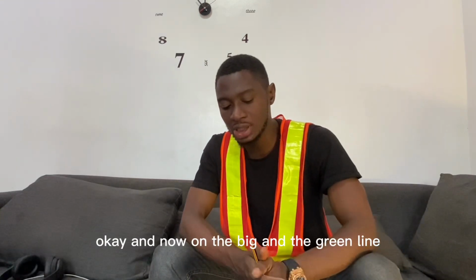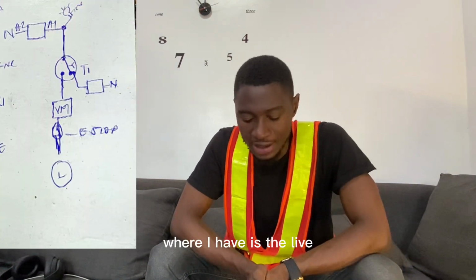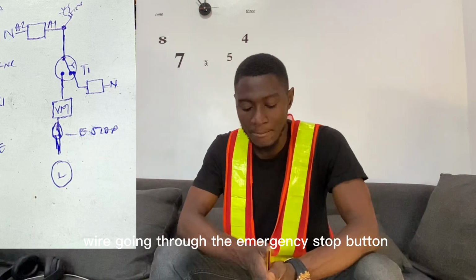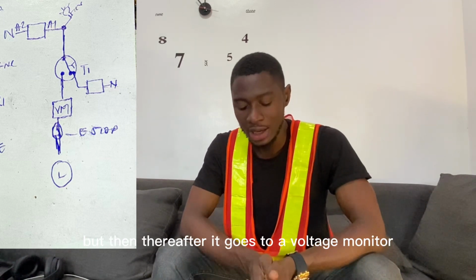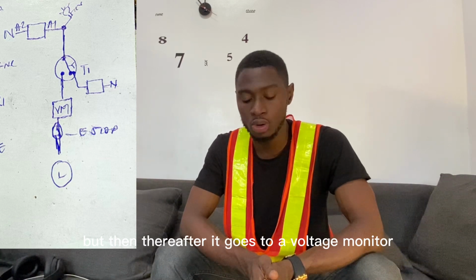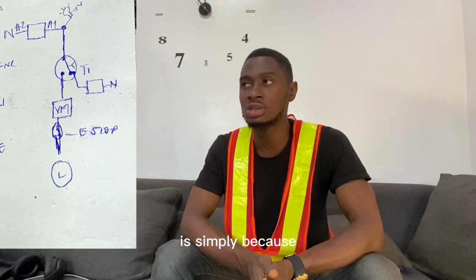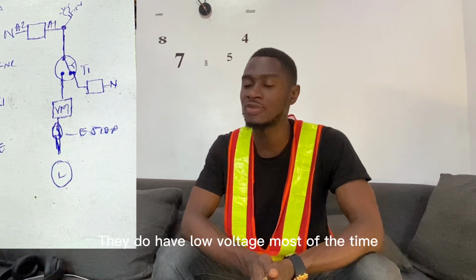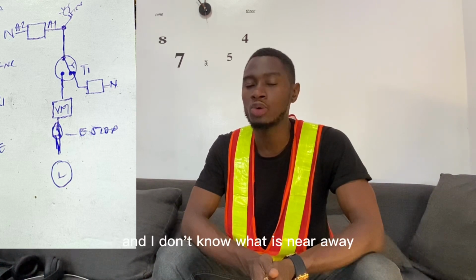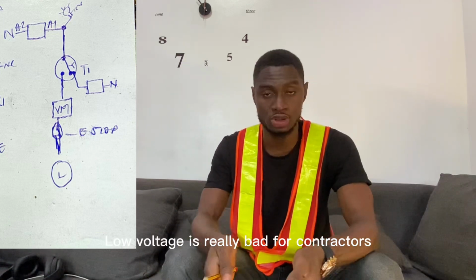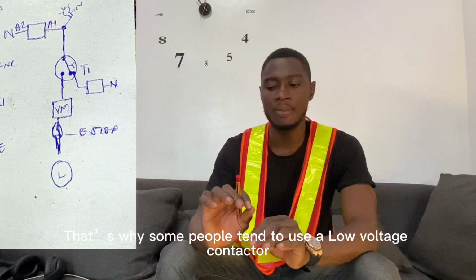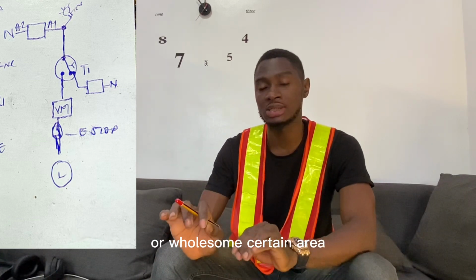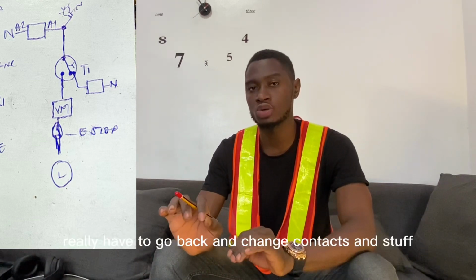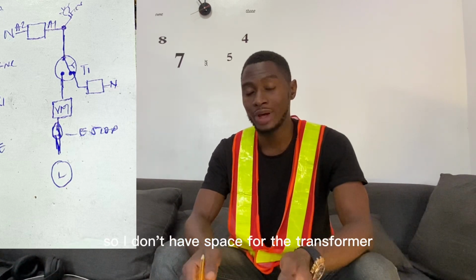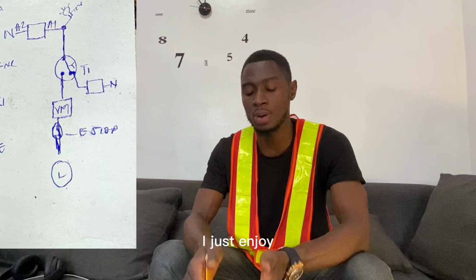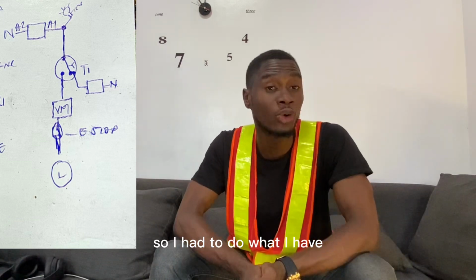Okay, now on the grid line, what I have here is the live wire going through the emergency stop button as usual. Thereafter it goes to a voltage monitor. The reason why I introduced a voltage monitor is simply because they do have low voltage most of the time, and low voltage is really bad for contactors. That's why some people tend to use low voltage contactors for certain areas, because we don't want a situation where they have to go back and change the contacts and stuff. I don't have space for a transformer, emergency job, so I had to do what I have.